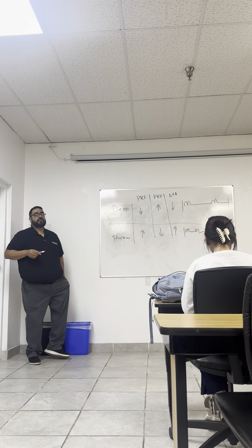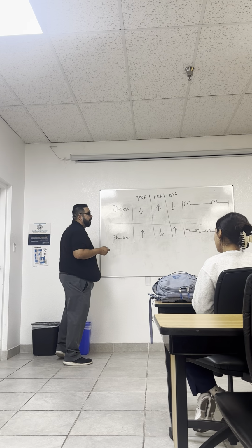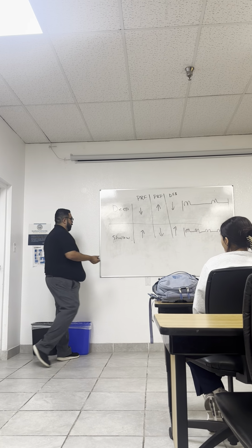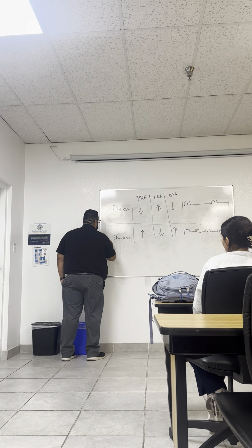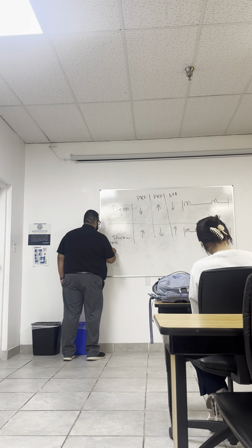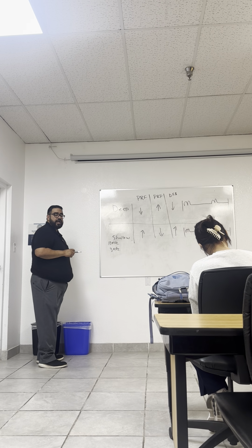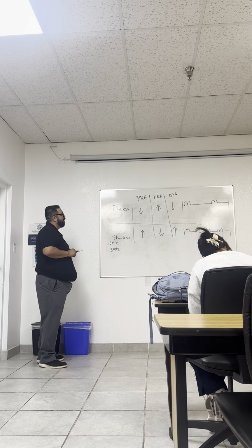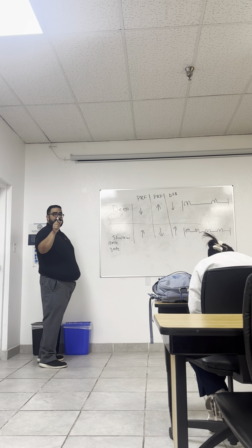Okay, so how do we figure out the duty factor? Pulse duration over PRP. Okay, so I have 2 transducers. One is a 10 megahertz transducer. The other is a 3 megahertz transducer. Which one has a higher duty factor? The 3 megahertz. Why do you say 3?